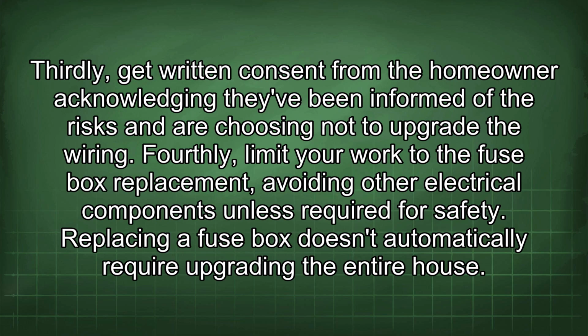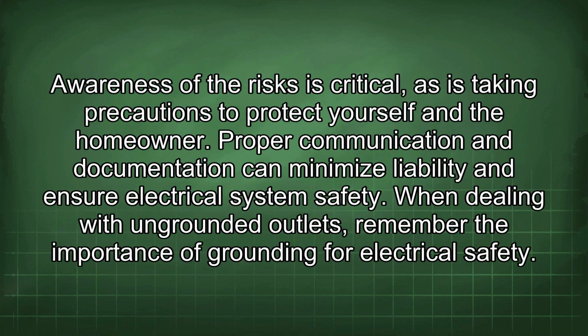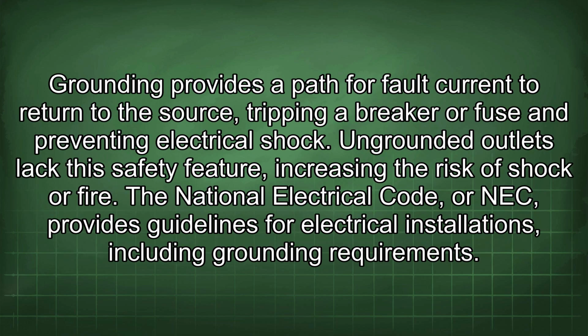Replacing a fuse box doesn't automatically require upgrading the entire house. Awareness of the risks is critical, as is taking precautions to protect yourself and the homeowner. Proper communication and documentation can minimize liability and ensure electrical system safety. When dealing with ungrounded outlets, remember the importance of grounding for electrical safety. Grounding provides a path for fault current to return to the source, tripping a breaker or fuse and preventing electrical shock. Ungrounded outlets lack this safety feature, increasing the risk of shock or fire.